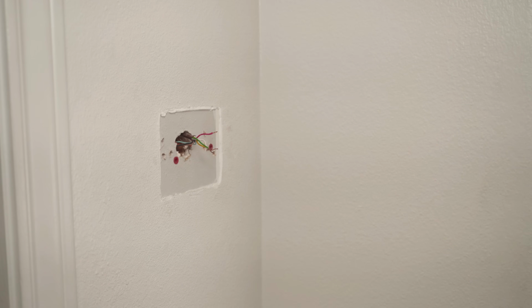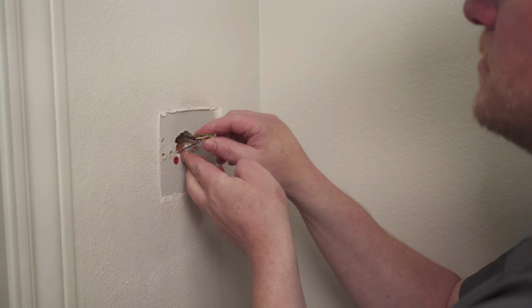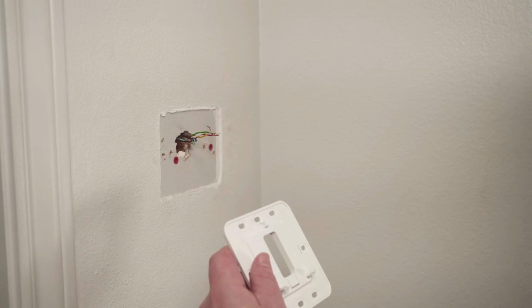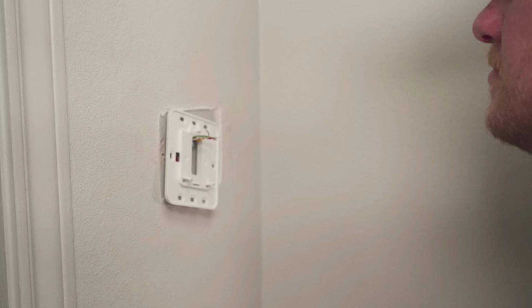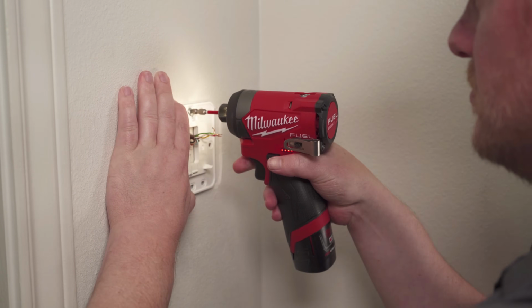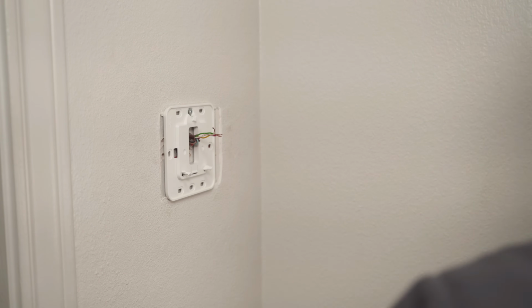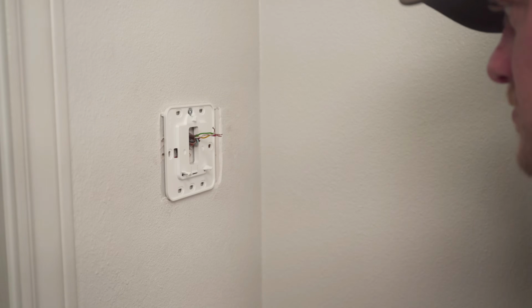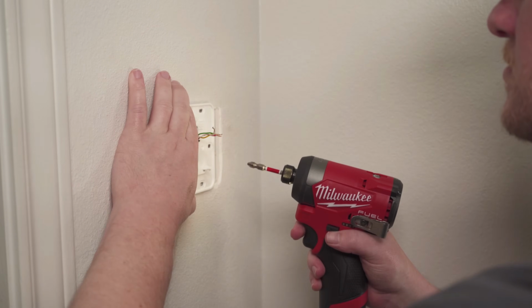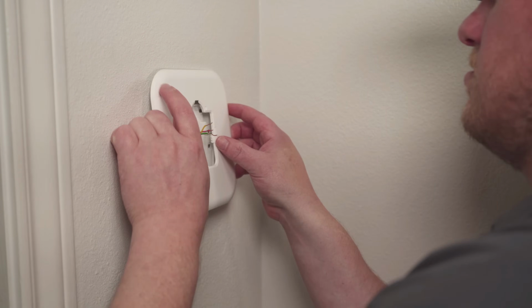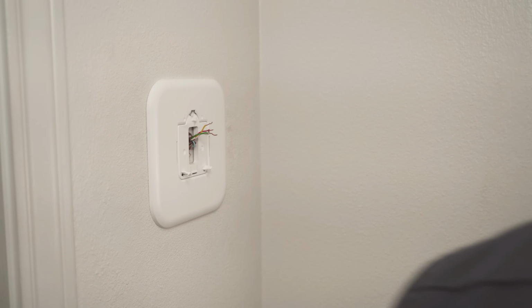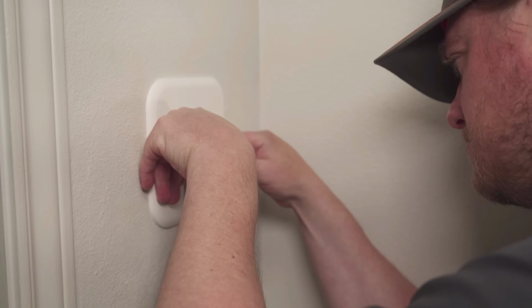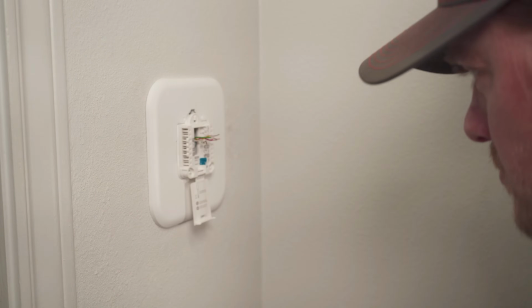That way we can set it up to have a more isolated test. So you can see that I actually have more than 4 thermostat wires here, but this being a commercial building, things get moved around all the time because each tenant often occupies the space differently from the previous tenant. A lot of times the thermostat wires get spliced up when things are moved around. So even though I have more than 4 wires here, I only have 4 good thermostat wires, so we still need to use that common wire adapter.